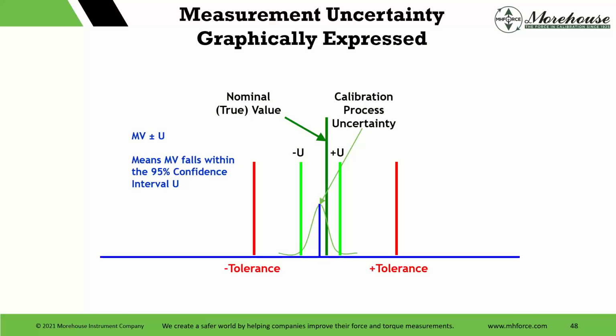And here, I'm going to plug Morehouse because it's what we have. If I use one of our meters, the 4215 plus, or our new C705P, I can program in coefficients, and when I send that cal out, I can get my results. And then I can get a new set of coefficients that'll bring them right back in, and I don't have to pay for 2 calibrations, adjustments, and everything else.